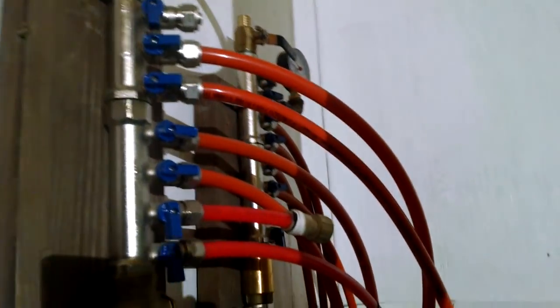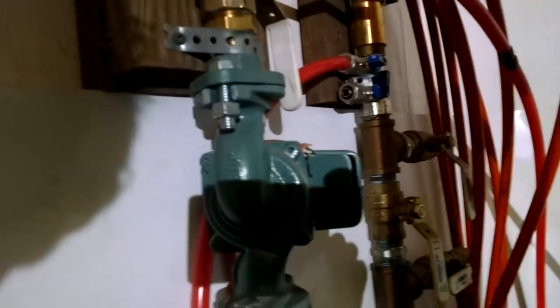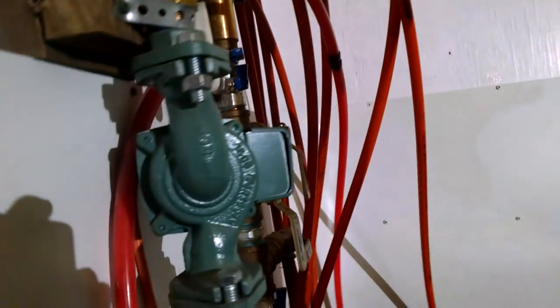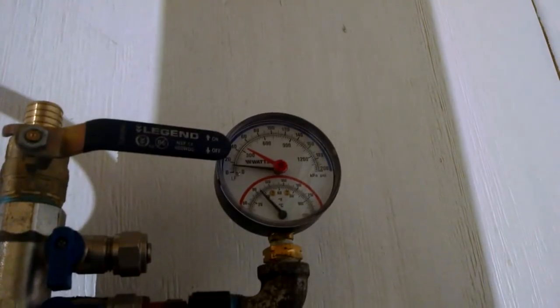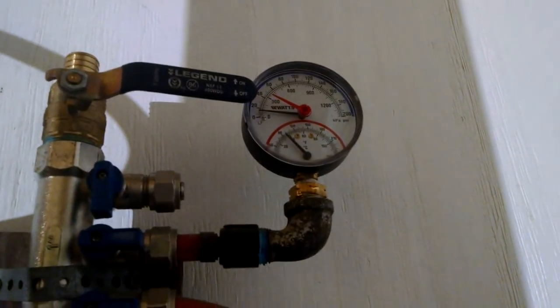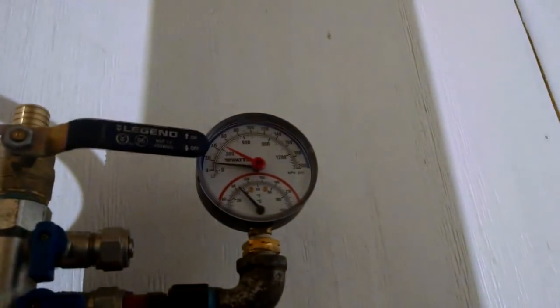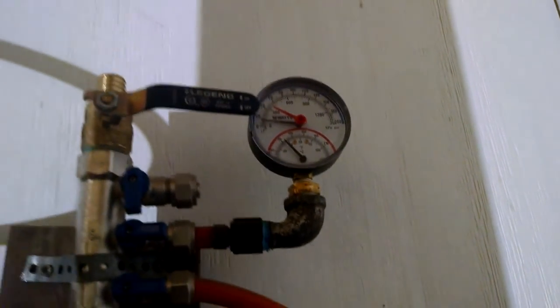Upon priming, you want that to be at the high pressure. It's just easier for the pump to circulate all the water and get all the air bubbles out of the system. And what you'll hear is that once all the air bubbles are out, the pump will get really quiet, like right now. The arrow on the top is the pressure, showing about 12 PSI. The bottom arrow there is temperature.